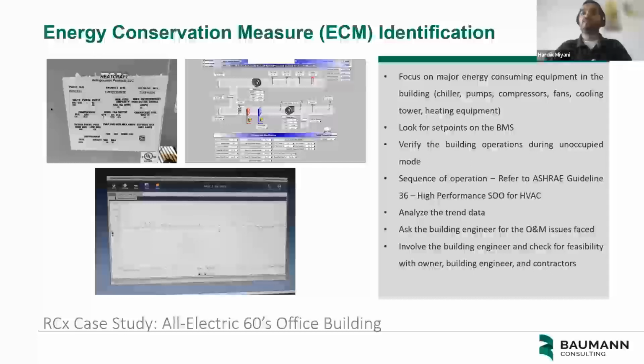Some things that we look for as part of this project are whether the equipment is working on schedule. For example, is there a schedule set for the air handling unit, or is it operating during unoccupied mode as well? Are there separate heating and cooling set points for the occupied and unoccupied modes? And is the equipment working as per the sequence of operation? Since the building was constructed in the 1960s, there are high chances the sequence of operation might have changed from the way the building was originally designed. Or the building engineer might have overridden the set points at some point and forgotten. These are some things that we usually look into in order to identify ECMs.